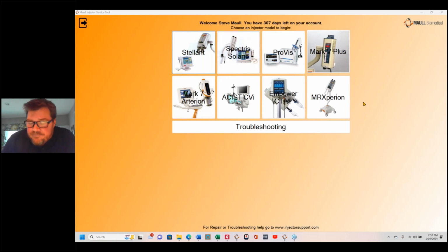As an example, one of the things they do on the Stellant that we just showed was plunger position calibration. Basically, if the display says there's 50 milliliters of fluid in the syringe, there's actually 50 milliliters of fluid in the syringe. That's a check we do. Now, how we do that check and how MedRad does that check are dramatically different, because MedRad has their own proprietary software they call Swift. If an adjustment needs to be made, say it's supposed to be 50 but it's at 45, they'll go in with their Swift software and electronically adjust the voltage on a potentiometer, or in some fashion adjust its resistance, so that position on the potentiometer now means 50 milliliters of fluid.